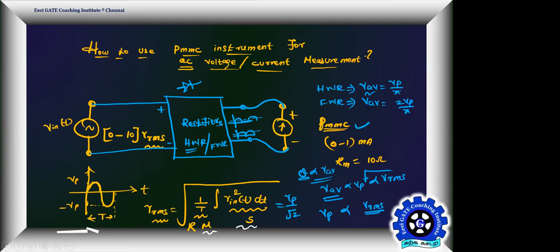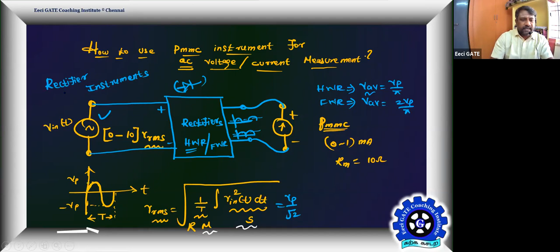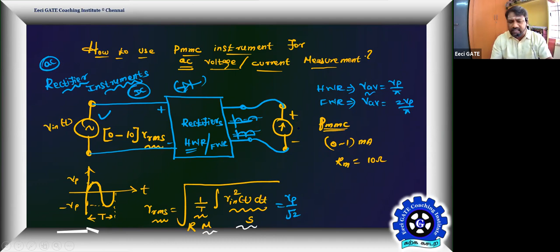So when you have a PMMC in your hand, you can take one diode from the laboratory and make your entire setup ready for measuring an AC signal by using a single extra diode. We call them rectifier instruments. A rectifier instrument uses PMMC only. Rectifier instruments are capable of reading AC, but we measure AC only by using DC. The rectifier is the interface between your input to be measured, which is AC, but the meter demands average, that should be a DC. So how to convert the AC into pulsating DC? With that, the instrument will happily respond. Therefore, you need a simple rectifier. It can be a half wave rectifier or a full wave rectifier design. In general, we call them rectifier instruments.